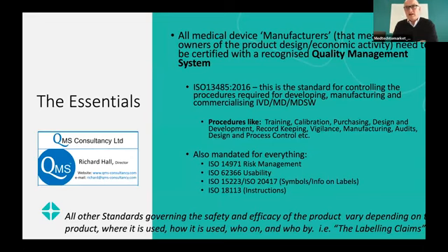And that is really a framework of procedures that you have to be compliant with so that everything has been done properly. So you've trained your staff, you've calibrated all your fridges and your pipettes, etc. You're following a procedure for design and development. So that's just an overarching quality management system, a bit like ISO 9001, which is a generic quality management system. But within medical devices, there are also 4 other standards which are mandated in order to launch your product. And that is the risk management standard, a usability standard, so you have to consider how your products are going to be used, and then 2 relating to the instructions and the symbols and the labeling that you use on your product.